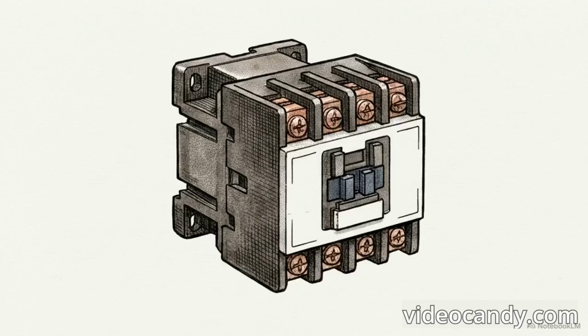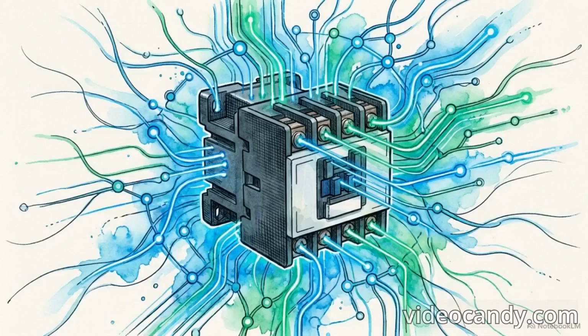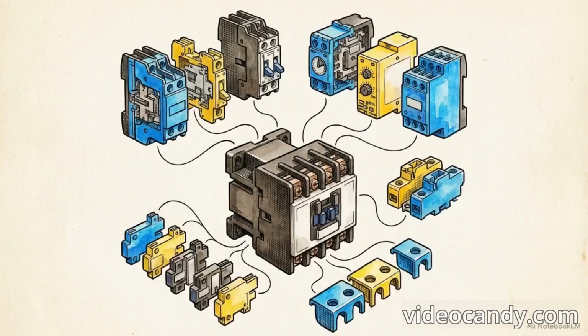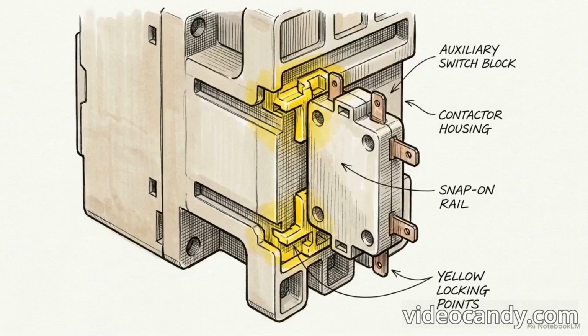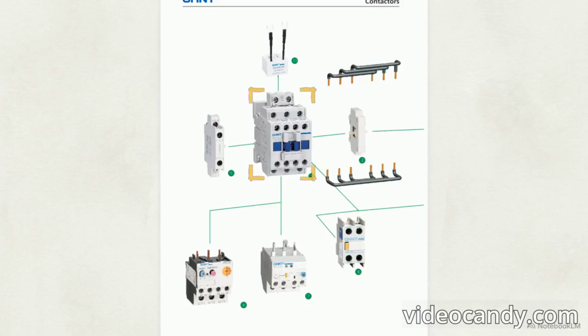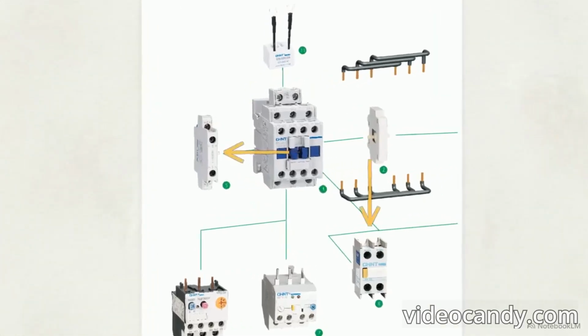A contactor proves its engineering value by surviving this violent plasma arc millions of times without failing. A standalone contactor provides no inherent data to a control system. It requires integrated logic and feedback mechanisms to coordinate its state with the wider automated network. Modern designs rely on a modular ecosystem. The base unit acts as a central physical hub where specific logic accessories can be snapped firmly into place.